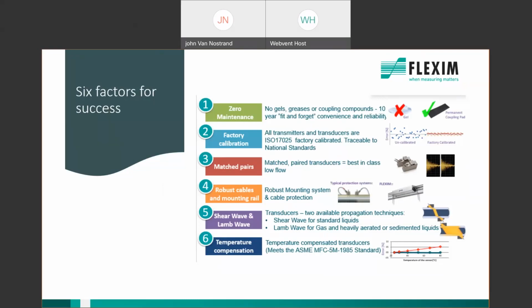There are crystals inside the transducers, and these are like diamonds. You can cut them to the same size and weigh them to the same weight, but each has its own individual signature. So the differences between those upstream and downstream transducers need to be canceled, and that's done with calibration. We do that at the factory, and every pair of transducers that we ship has a calibration certificate, as well as the meter having its own calibration certificate.